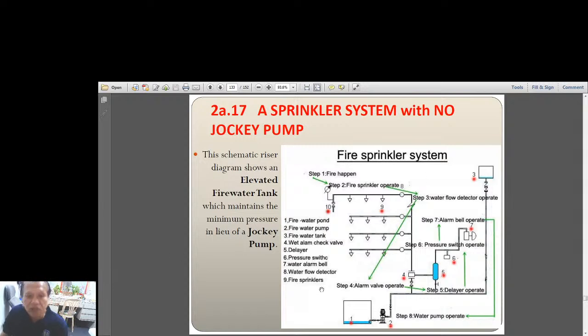What is the advantage of this? Well, there is no jockey pump that is every now and then running, consuming electricity. Why is the jockey pump running all the time? Yes, to maintain the pressure. And why does it need to continuously run? Of course, sometimes there would be leaks in the piping, especially in the check valve of the pumps. There would be loss in pressure because of the leak in the gate valves and in the check valves.